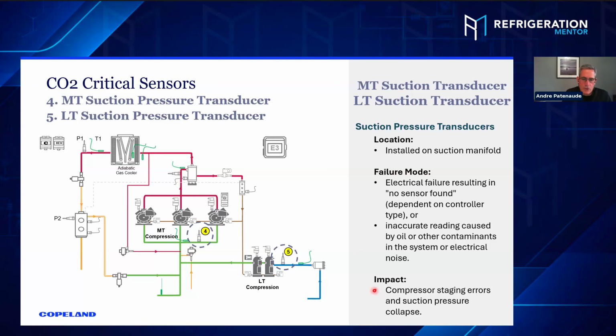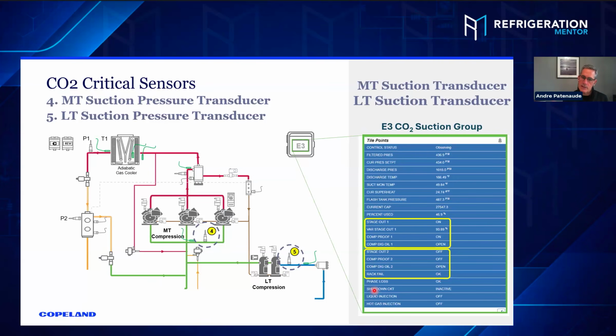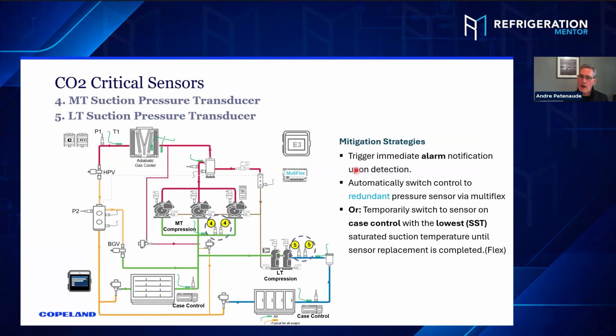And compressors don't run. Of course, it's pretty obvious your system's down. And again, in the E3, you can see exactly what's going on with your points, your suction groups, stage 1, stage 2, and understand what they're doing. So that information is there through the E3 to look at. So from a mitigation strategy, again, same thing. If you do have redundant sensors, you can tie them to a MultiFlex board and just switch over. But if you don't, it's a simple solution here. You temporarily switch the sensor to the lowest SST pressure transducer on a case. Yep. That will get you to limp along until the service comes in to replace that pressure transducer, whether it's on the medium temp or on the low temp.